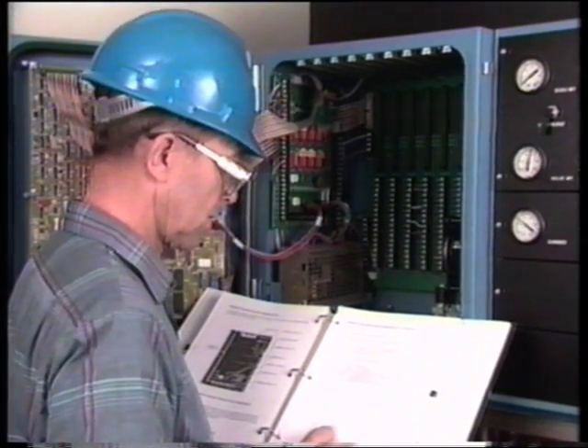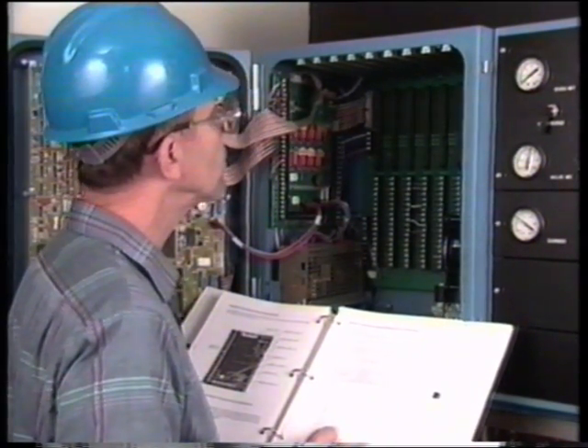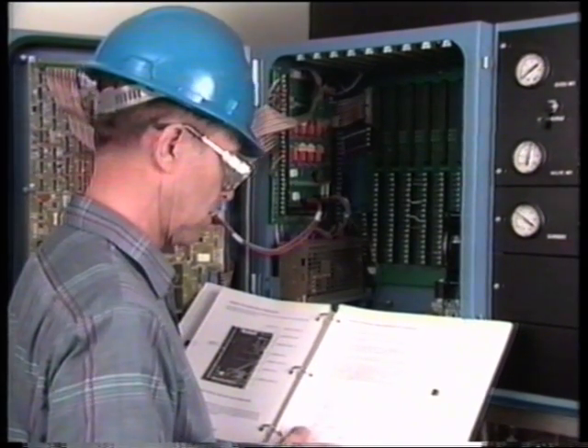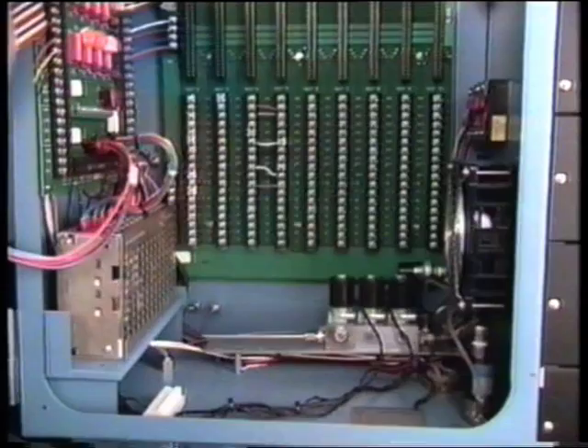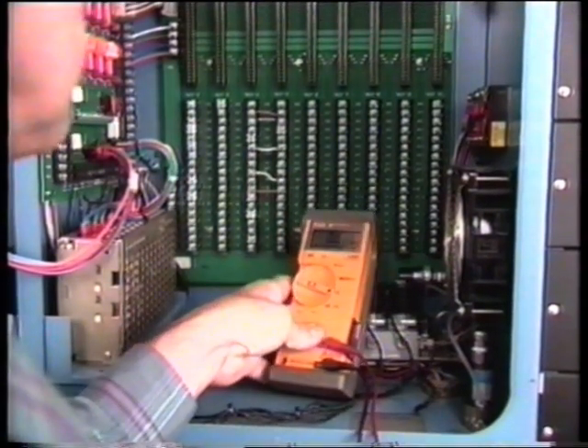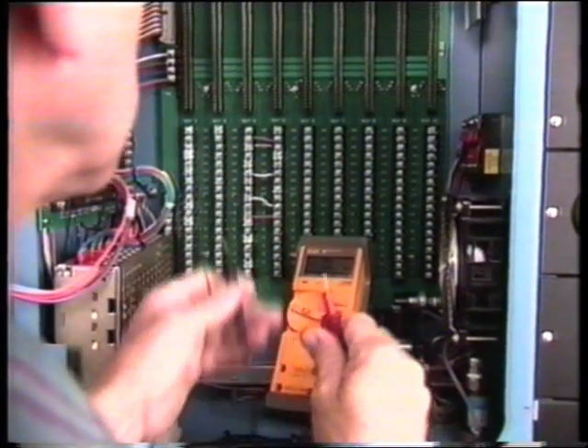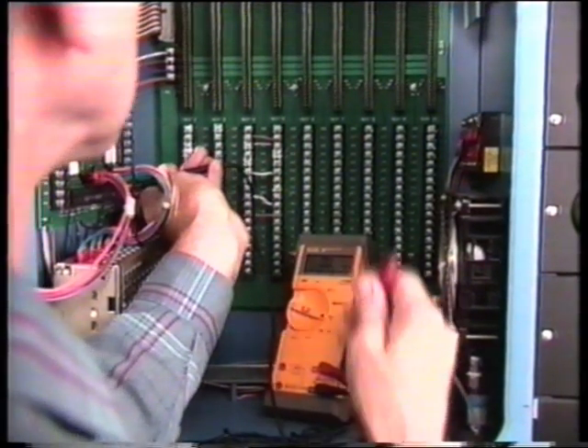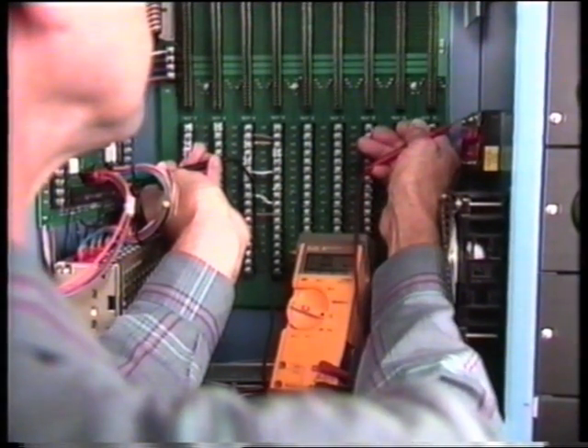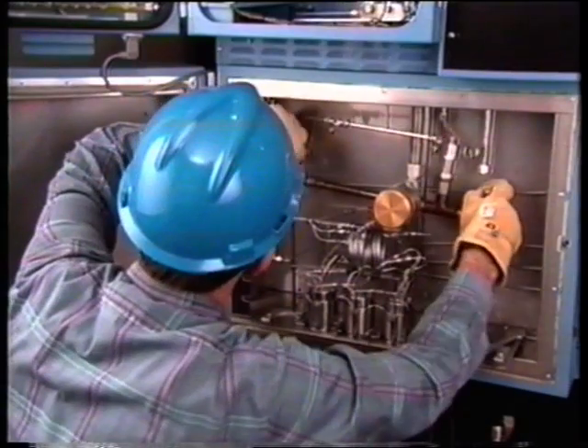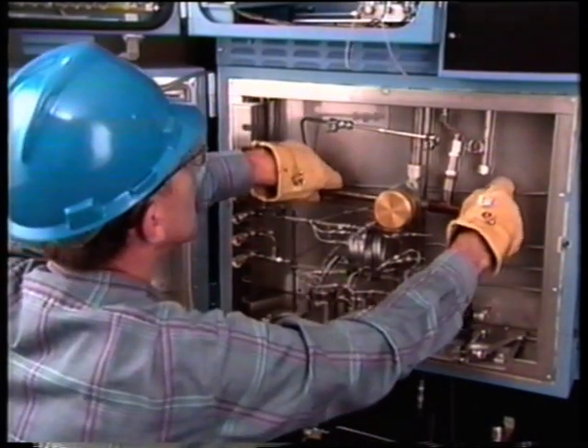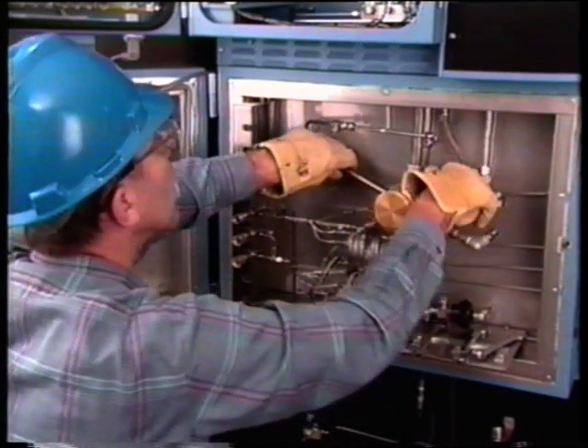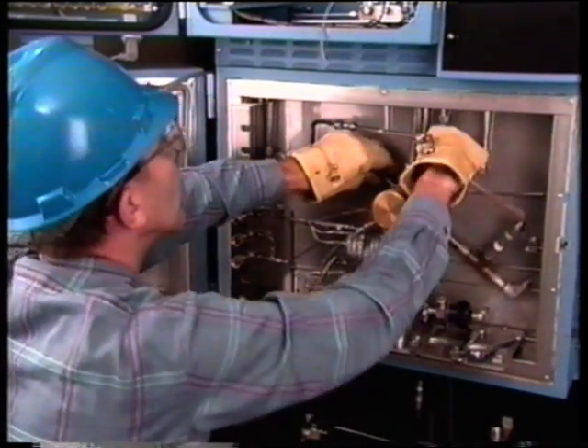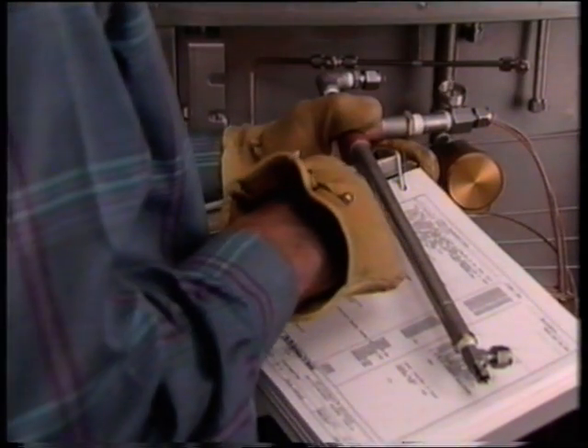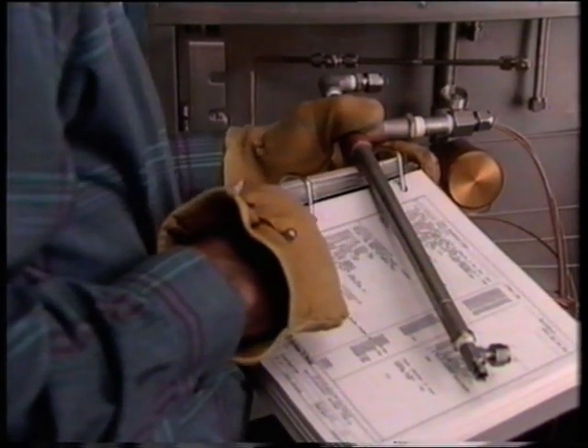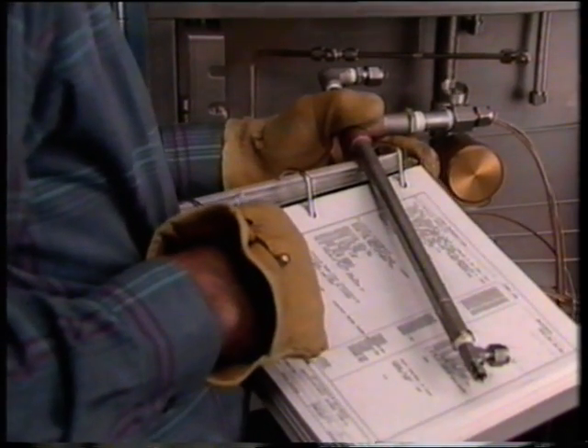On this model, it's not necessary to disconnect the heater leads because the circuit contains a solid-state relay which opens when the power is off. Connect one lead to each terminal and check the resistance reading. A reading of infinity indicates an open element, and a reading of 0 indicates that the element has shorted. Since the heater element is open, we'll replace the heater assembly. Loosen the fasteners that secure the heater and remove it from the oven. Before installing a replacement heater assembly, make sure that the new element meets the requirements of the analyzer and the process.